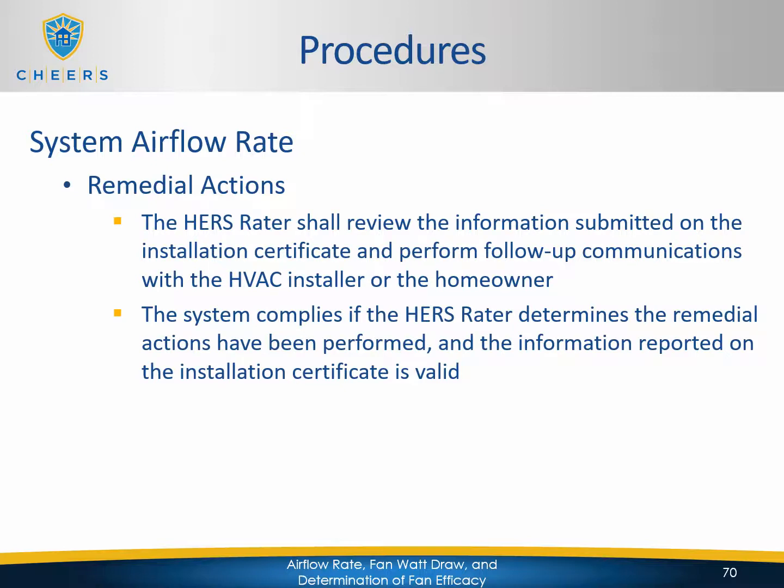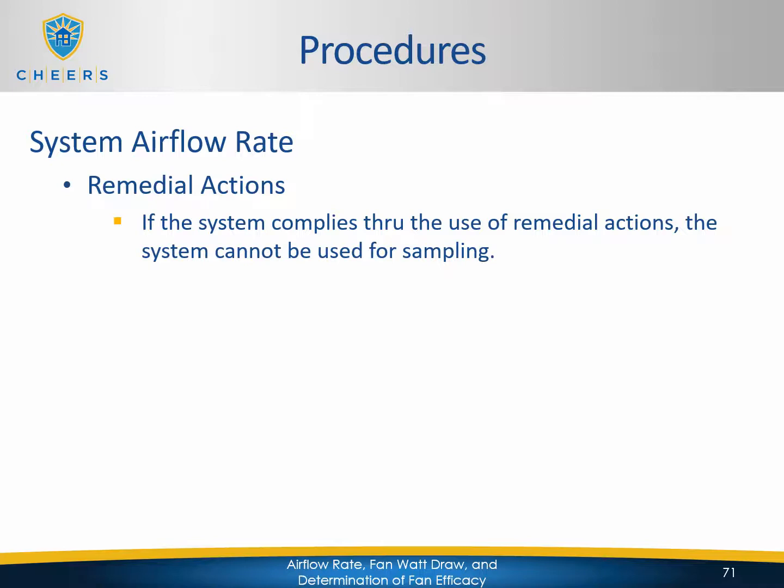The HERS Rater shall review the information submitted on the installation certificate and perform follow-up communications with the HVAC installer or the homeowner. The system complies if the HERS Rater determines the remedial actions have been performed and the information reported on the installation certificate is valid. If the system complies through the use of remedial actions, the system cannot be used for sampling.